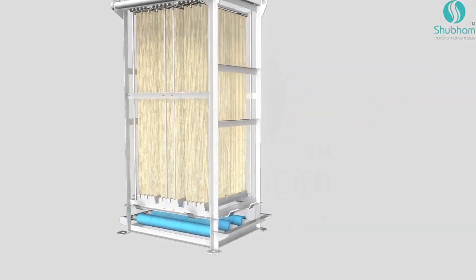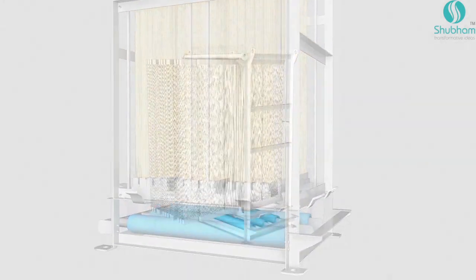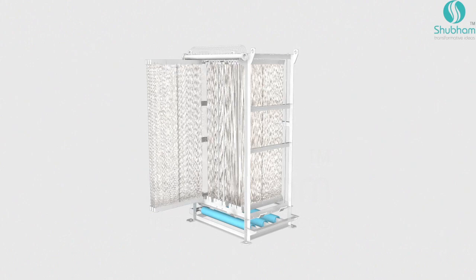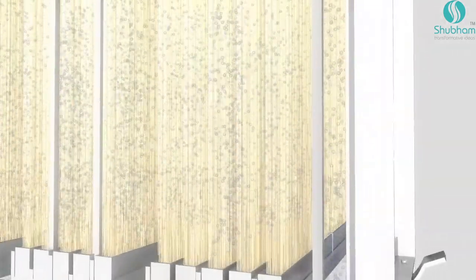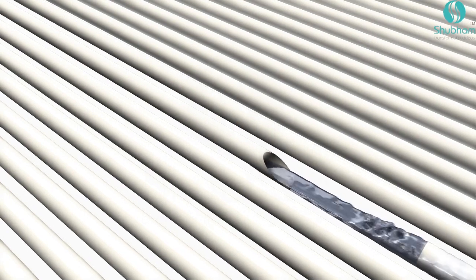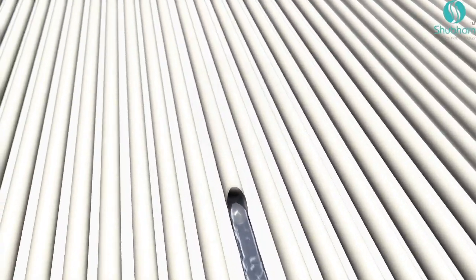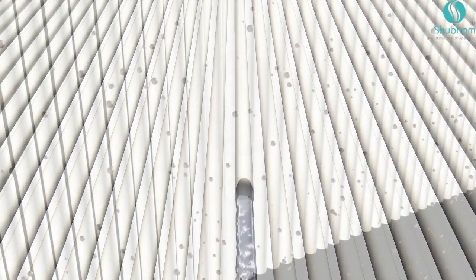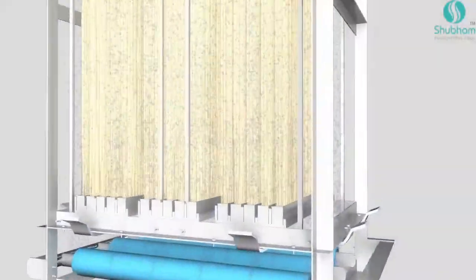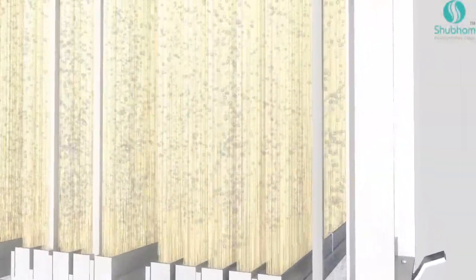In the next stage, a collection of submerged membranes takes over the process. Membranes are housed in modules that are in turn assembled into cassettes. Made of millions of ultrafine fibers, these fibers allow clear water to pass through while restricting pollutants outside. Each module has its own continuous and automatic cleaning system, where air keeps scouring the membranes throughout the process.